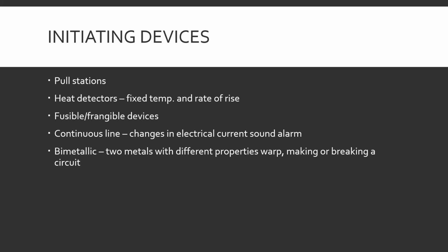Rate of rise is a little different. It's set to go off at a certain number of degrees, based on how rapid the temperature changes. I know this one's later on, but here's a quick version. If it's 60 degrees in a room and in a minute it jumps up to 80 or 90 degrees, it might set off the thing because it's getting really hot in here really quick. There must be a fire.